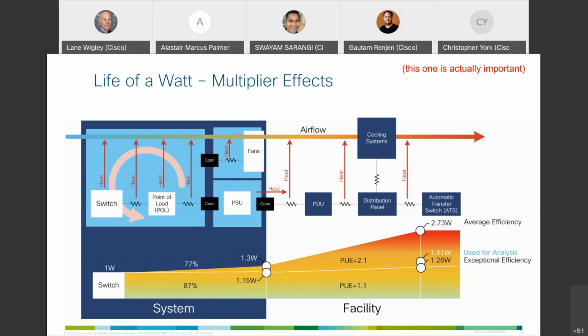As we're moving wire to wire over the PCB, some heat is lost from that, and quite a bit of heat is lost from the ASIC itself. The point of load devices do that final step of conversion. Remember, we started up at 500 kilovolts, and eventually come into the router at either 48 volt DC or usually 240 volt AC, sometimes a bit higher. The power supplies then convert that to either 12 volts or 54 volts, and eventually the point of load devices convert it to 1 to 5 volts, whatever the optics or ASICs need.